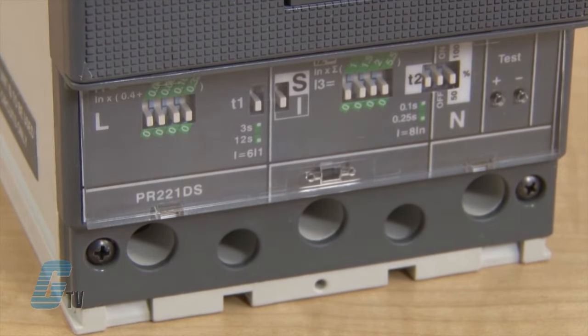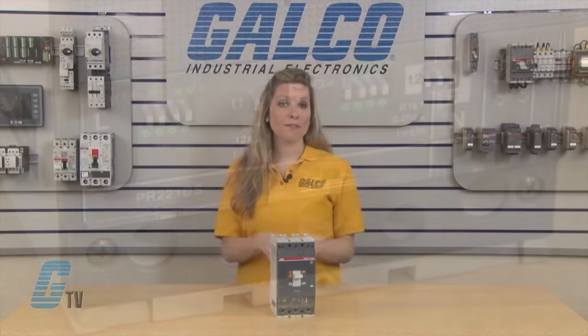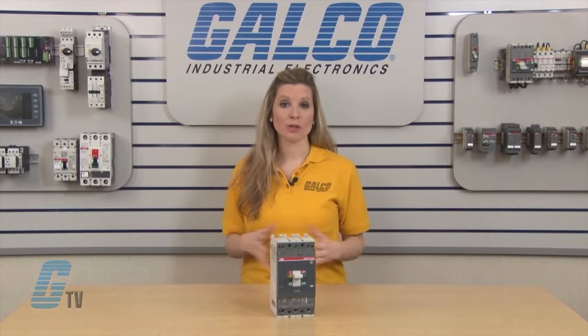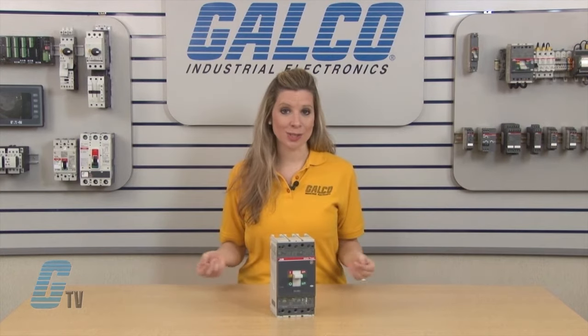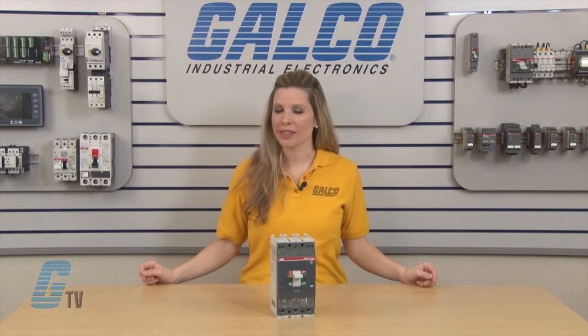I will be using the PR221DS dip switch setup. This offers protection against overloads with a long inverse time delay and short circuits with either an instantaneous or an inverse time delay trip.